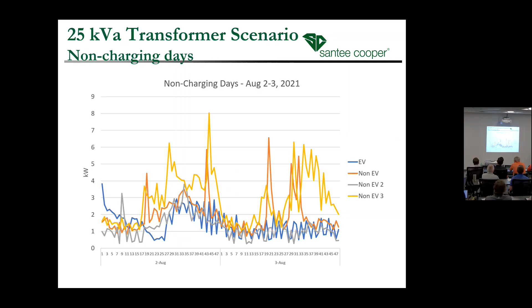Same thing here, I won't go into quite as much detail, but essentially you have a 14.8 kW customer with the EV. This is a 50 kVA transformer with a 40 amp charger. Again, the rest of these folks are non-EV customers, and obviously all of them have lower demand. This customer is getting close, but still about 3 kW less than the EV customer.